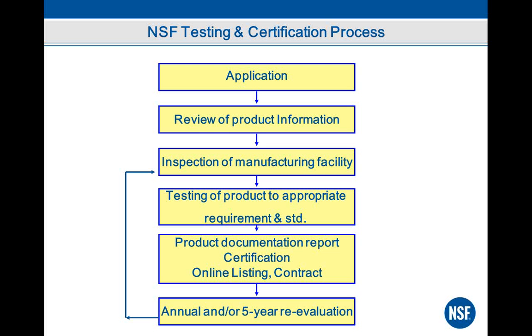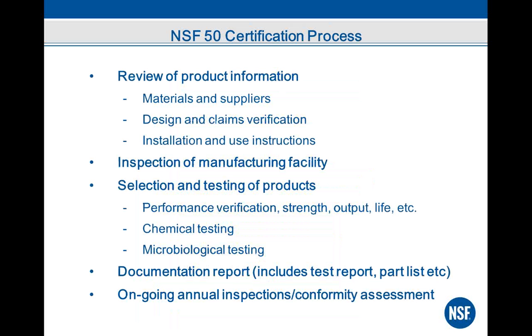Obviously, there's a review of materials, and that typically happens after a company applies for certification. You get into the details of their product to determine what is appropriate for testing or what requires testing. Obviously, there's a manufacturing facility audit. Then there's the compilation of the results of that testing. And then if the product passed the testing to serve as representation for the other products that the company produces, that company may be eligible for certification. So certification, again, is not just a one-time event. It's more like an ongoing assurance, a conformity assessment, so that there are annual inspections and then some period of reevaluation or retesting as well. Next slide, please.